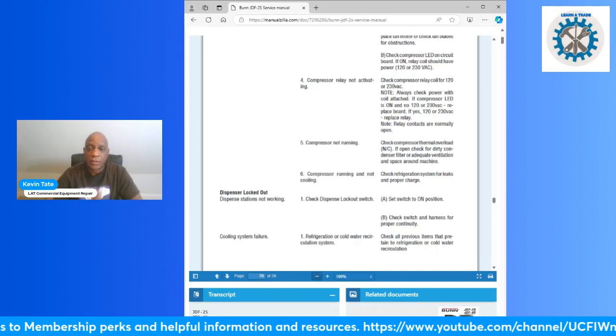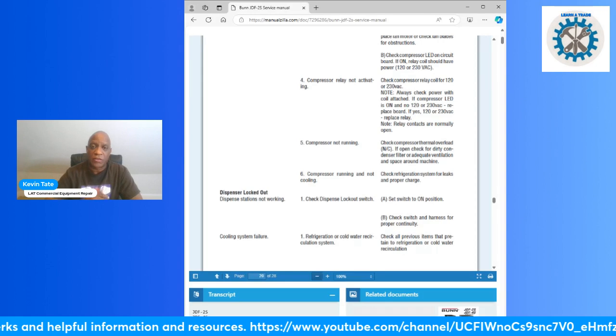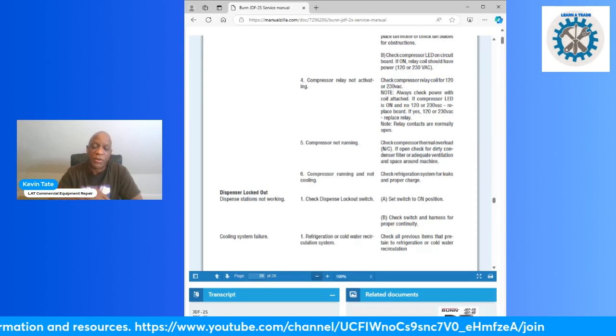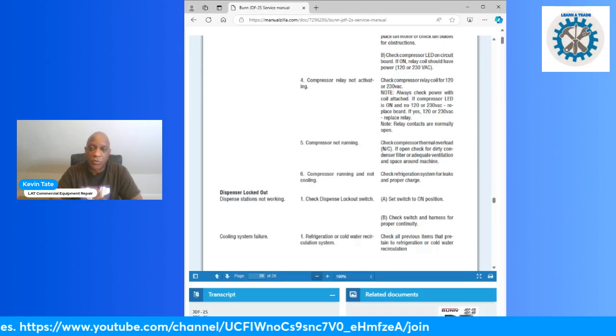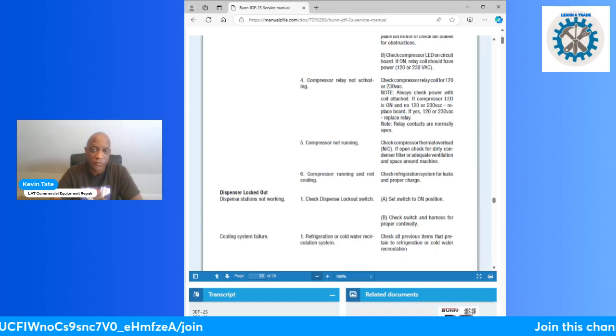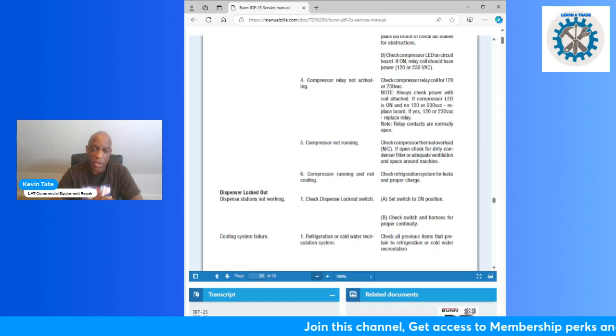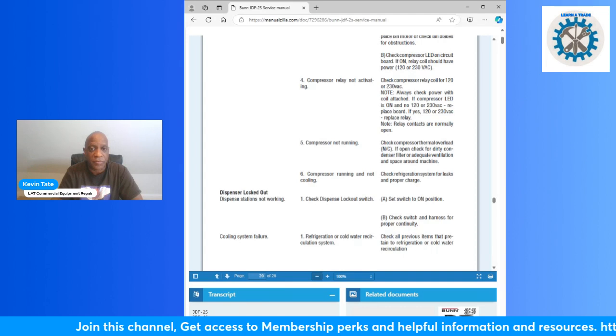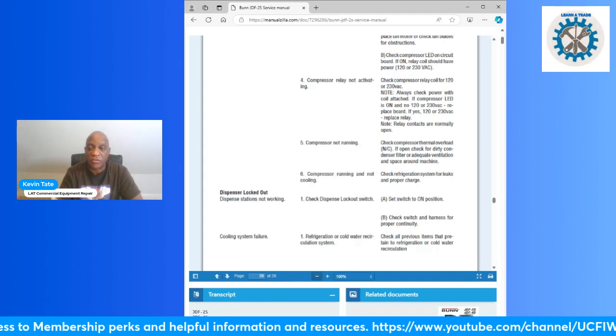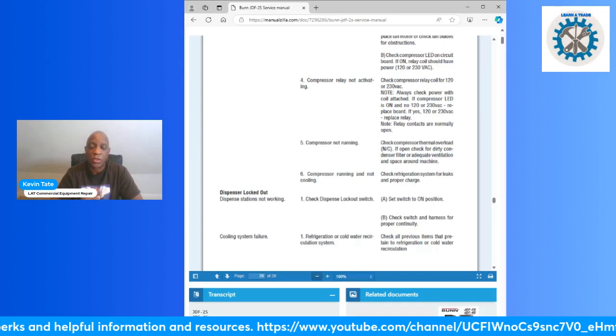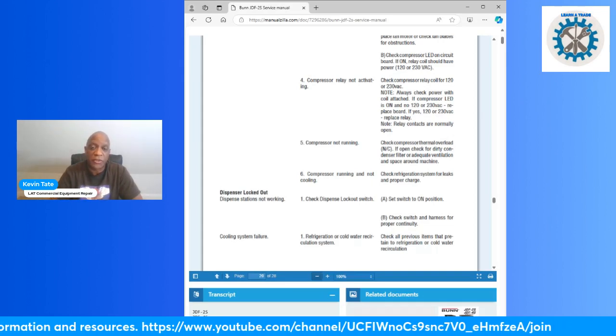And if you don't get that water level up to that point, the system will not function properly. It'll run for a little while, and it'll dispense, but it won't freeze. It won't cool down, because the system is not telling the compressor to turn on, because it's not sensing that water level. So that might be a simple fix for you out there.